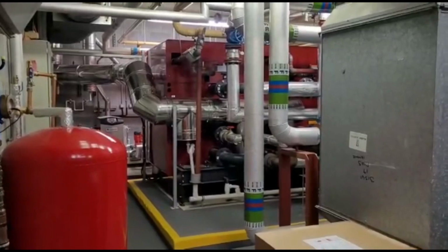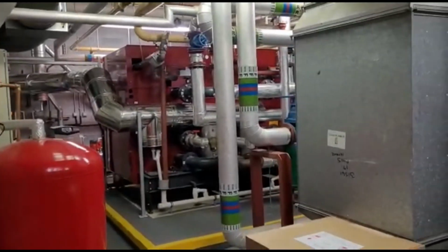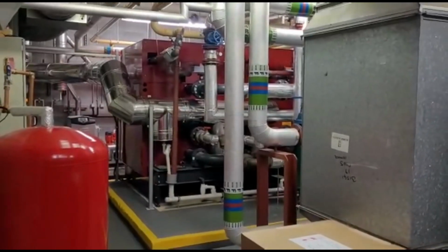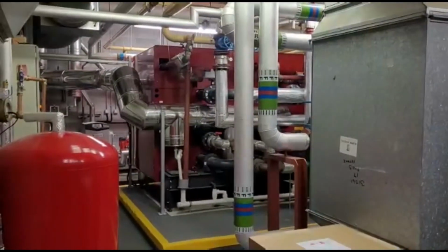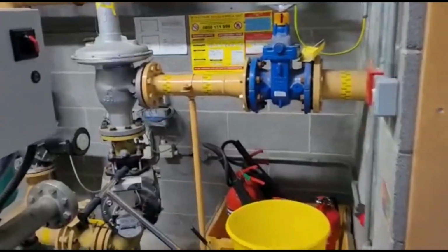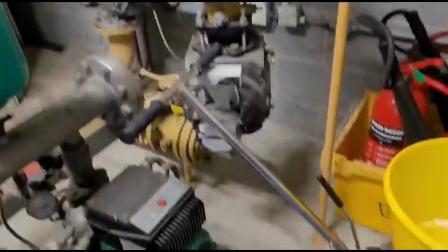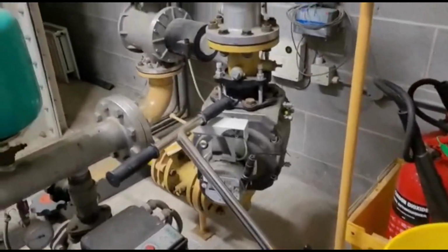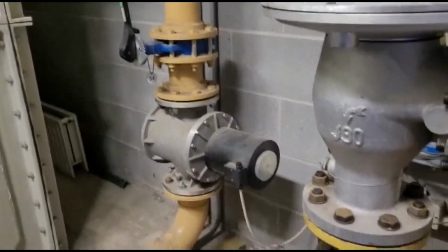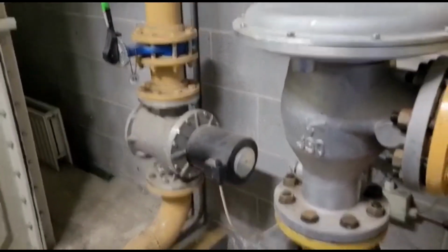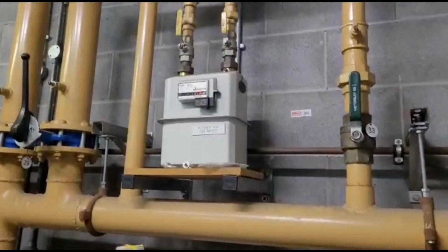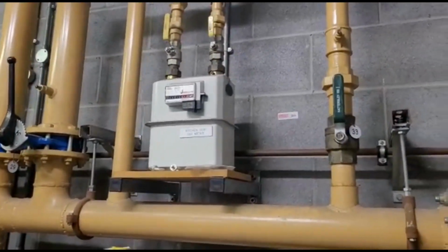Afternoon, Alan. Thought I'd do another plant room for you. Just take you on a bit of a tour. I'll try to make it as quick as I can. So yeah, cool, happy days. Right, so we've got his main incoming. Obviously your governor, rotary meter, gas solenoid, obviously because everything's tied with fire alarm and BMS system and all that lot. So, and it springs off, and secondary meter to kitchen's not exciting.